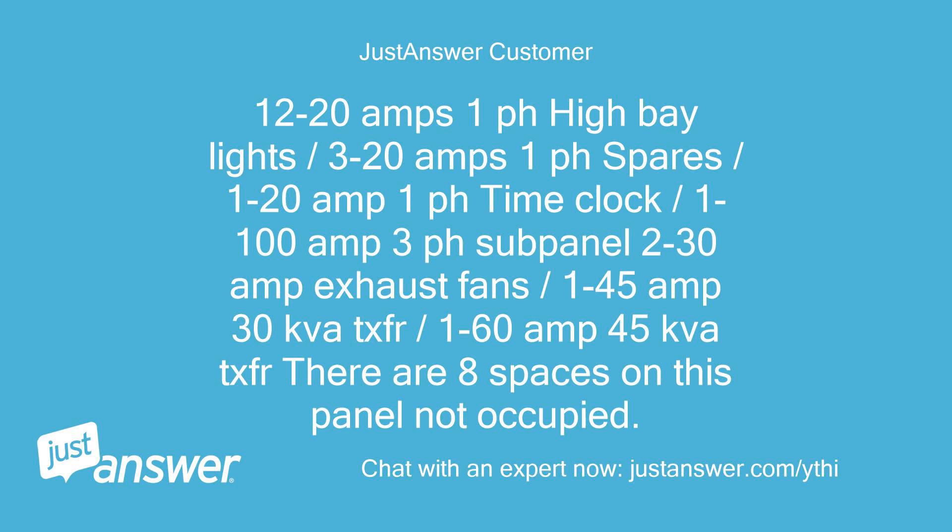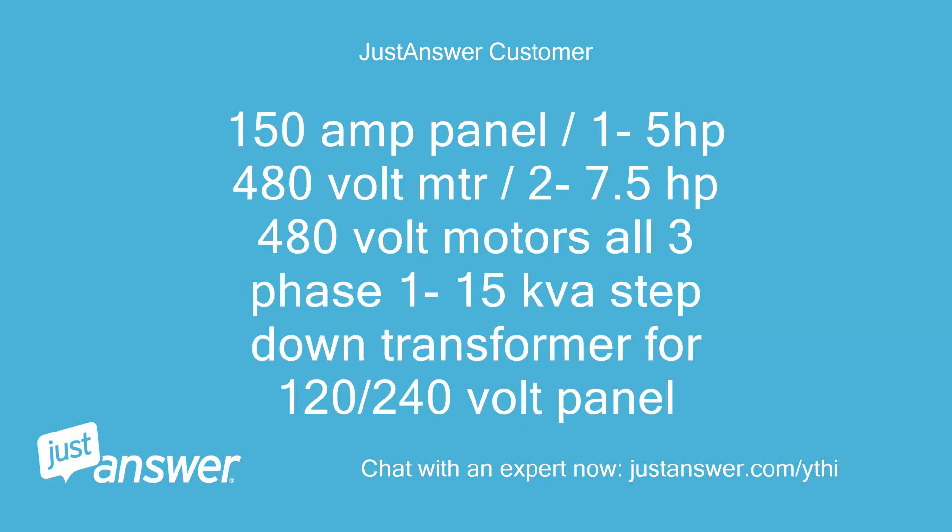Nameplate loads of equipment: 1-45A 30kVA transformer, 1-60A 45kVA transformer. There are 8 spaces on this panel not occupied. 150A panel: 1-5HP 480V motor, 2-7.5HP 480V motors, all 3-phase, and 1-15kVA step-down transformer for 120-240V panel.